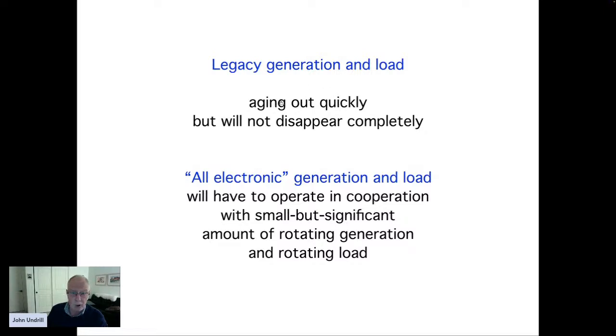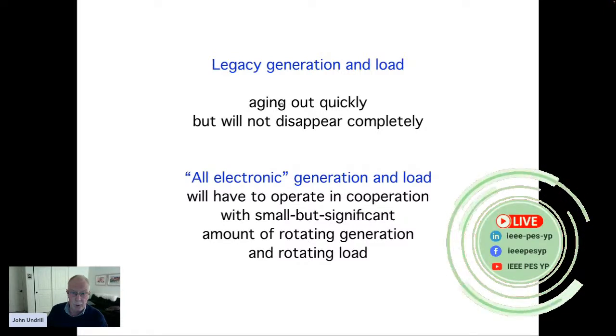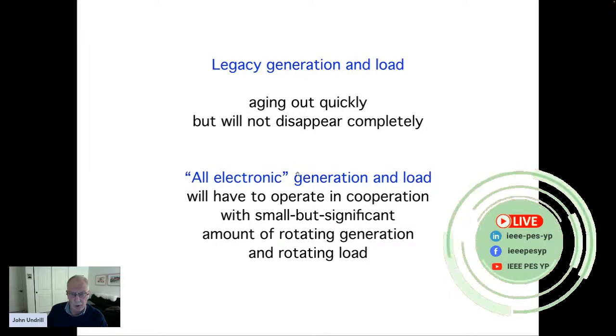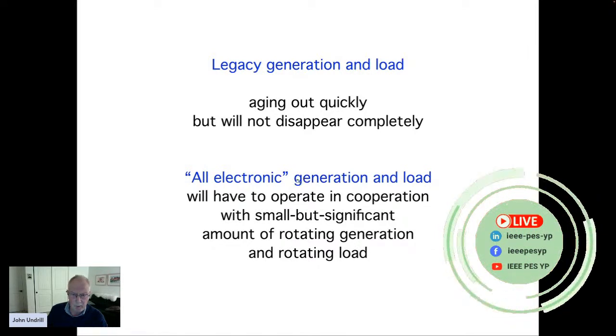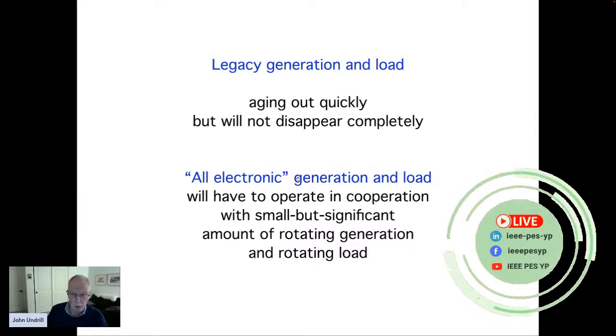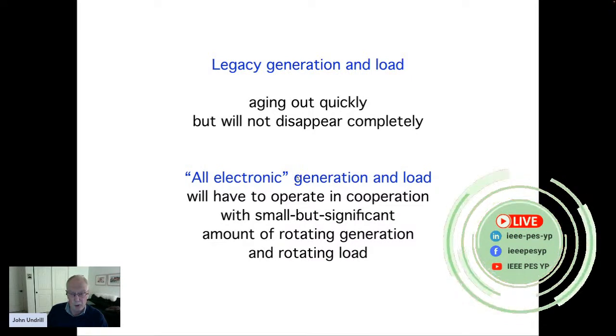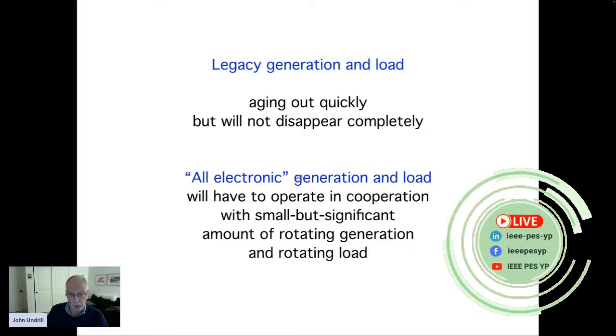We're getting rid of coal burning plants as fast as we can. There's a conference going on in Egypt now discussing that subject. It's not going to be easy if your natural resources make you dependent on coal, but eventually we can expect that the large thermal plants will disappear. We are going to an all electronic generation and load system. The generation will be electronic, solar panels with inverters. The other part of the electronic generation will be wind turbine generators, producing power at variable frequency, maintaining the charge on a DC bus capacitor, and being turned into AC 50 or 60 cycle power by electronic inverters.